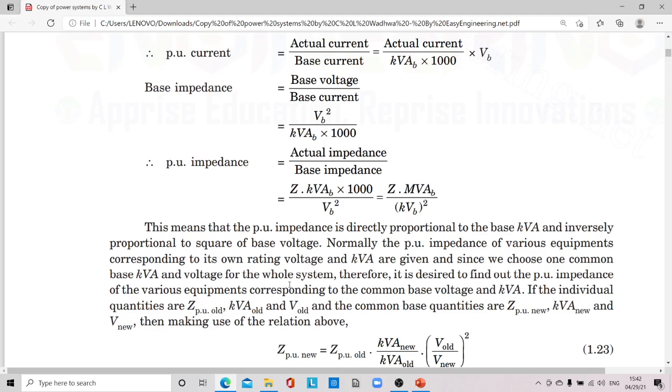With per unit system, there is less chance of making mistake in phase and line voltages. Single phase or three phase quantities, it can be anything. Also, per unit impedance of the transformer is same, whether it is referred onto primary or secondary side of the transformer, which is not the case when considering absolute value of these impedances.